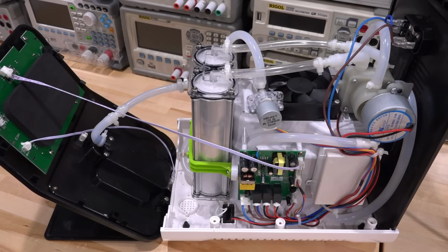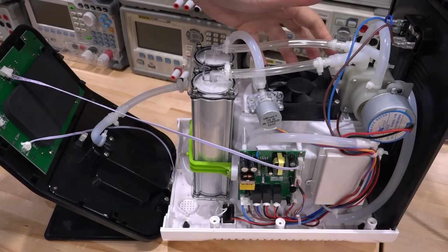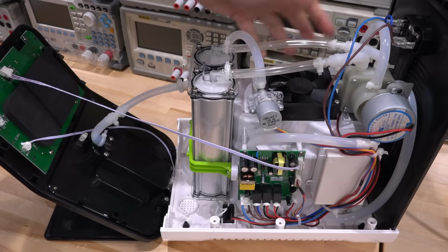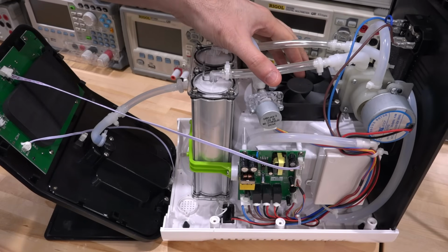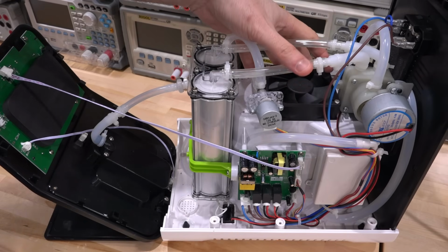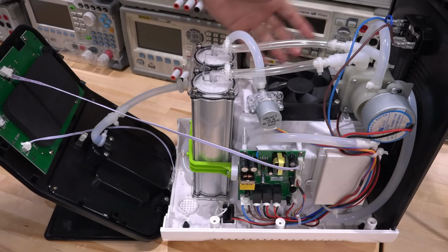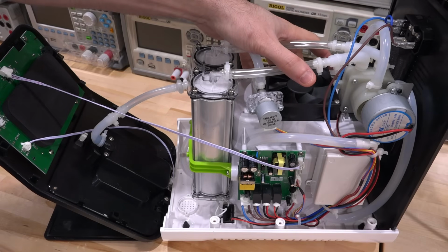And here is what is inside of our oxygen concentrator. If we look carefully, we should be able to identify all of the components in here and relate them back to the block diagram that we were looking at before. In the middle of all of this is another container where the compressor is. It's basically the compressor housing. And there's a fan here on top of it. And that is to cool the compressor as well as the air as it gets compressed so that it's passed to the rest of the system roughly close to room temperature.